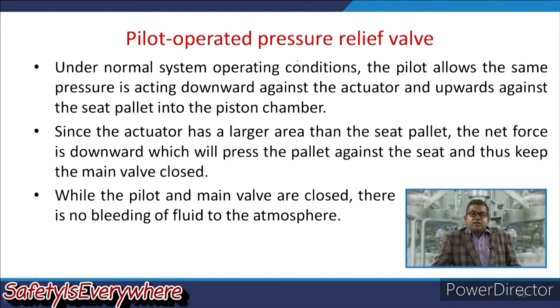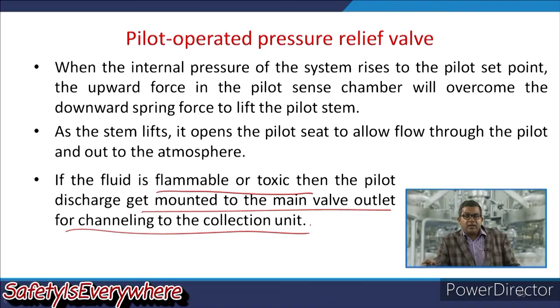When the internal pressure of the system rises to the pilot set point, the upward force in the pilot sense chamber will overcome the downward spring force to lift the pilot stem. As the stem lifts, it opens the pilot seat to allow flow through the pilot and out to the atmosphere. If the fluid is flammable or toxic, then the pilot discharge is mounted to the main valve outlet, channeling it to a collection unit so that it cannot go into the atmosphere and create further problems.